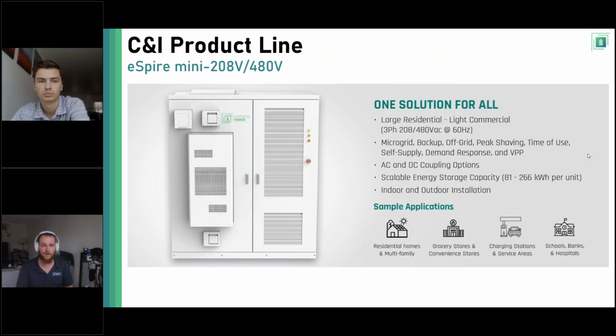But we can DC couple up to 135 kW of DC power directly into one of these Espire Mini units. What's great about that is you eliminate the need for a PV inverter. As long as you size your strings appropriately, you can feed them directly into the Mini, reducing installation costs and the lead times that come with PV inverters. I know some of the lead times for certain inverters have been off the charts. I think it's probably stabilized now, but our whole goal with this is to consolidate equipment and eliminate extra equipment like PV inverters and external transformers when we can.